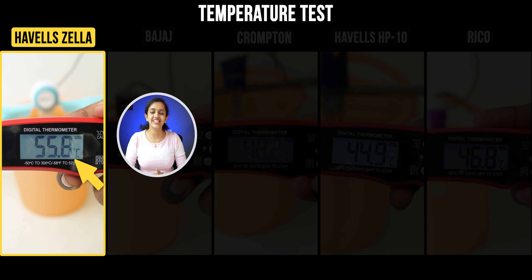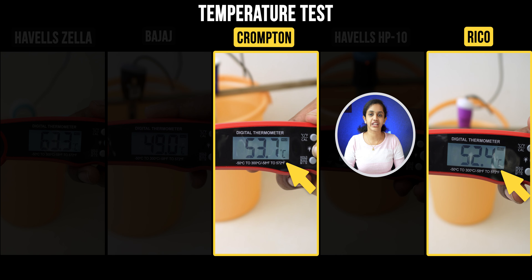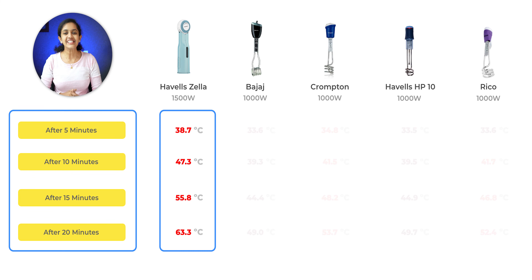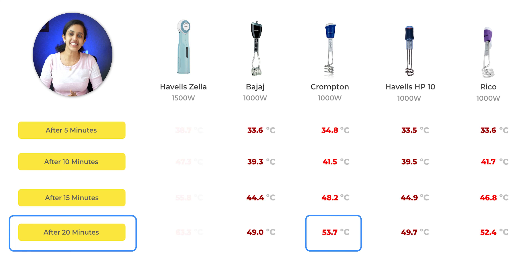The heating test runs at 5, 10, 15, and 20 minutes. At 5 minutes: Bajaj, Havells HP10, and Rico are around 33 degrees; Crompton is 34.8 degrees; and Havells Zella is 38.7 degrees. At 10 minutes: Bajaj and HP10 are around 39 degrees; Crompton and Rico are around 41 degrees; and Havells Zella is 47.3 degrees.